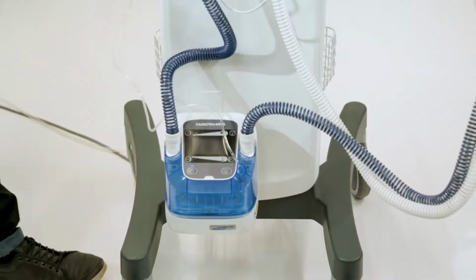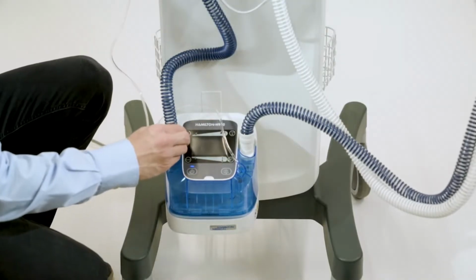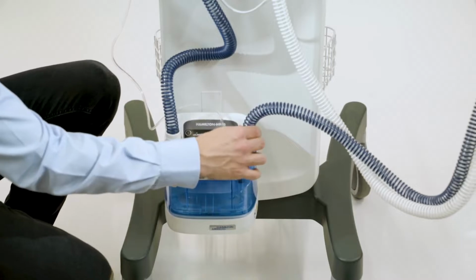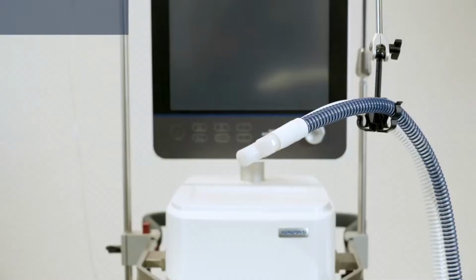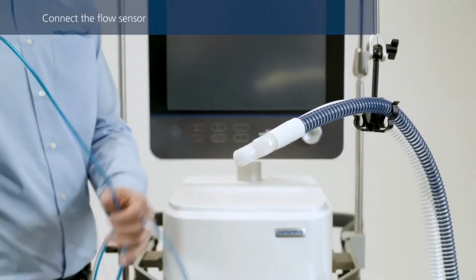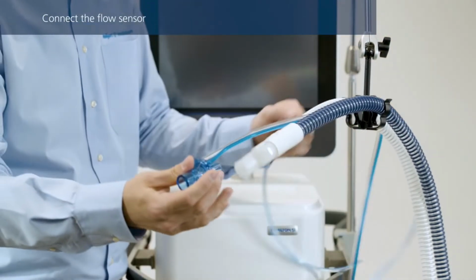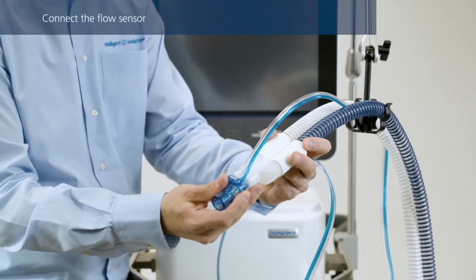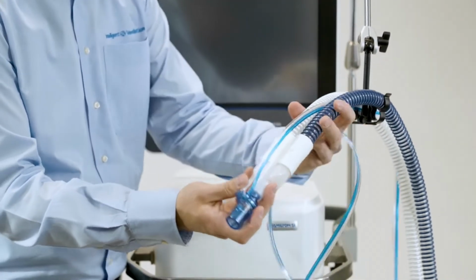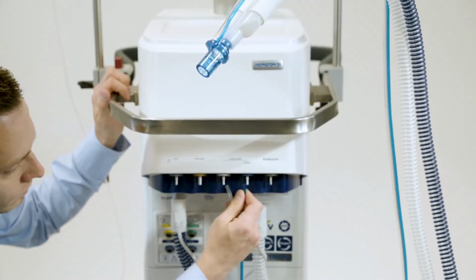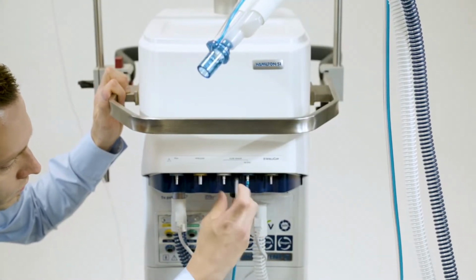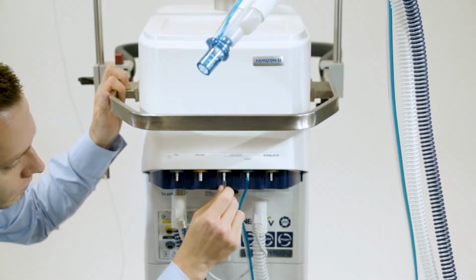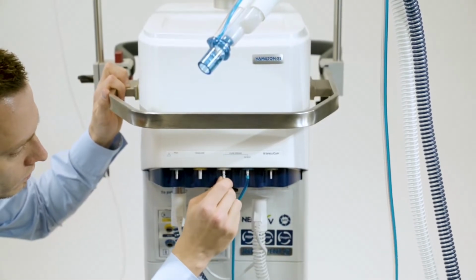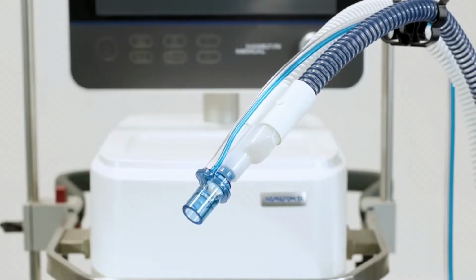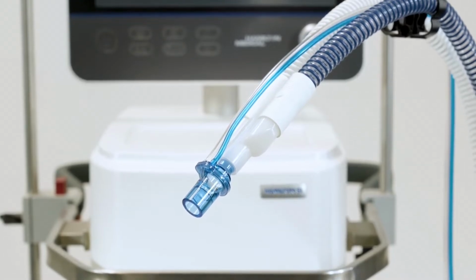Make sure that all electrical contacts on the breathing circuit match the connecting element on the humidifier. Insert a flow sensor into the breathing circuit in front of the patient connection, that is, the Y-piece. Attach the blue and clear tubes to the flow sensor connection ports on the ventilator. To prevent water accumulating in the flow sensor and tubing, position the flow sensor tubing on top of the flow sensor.